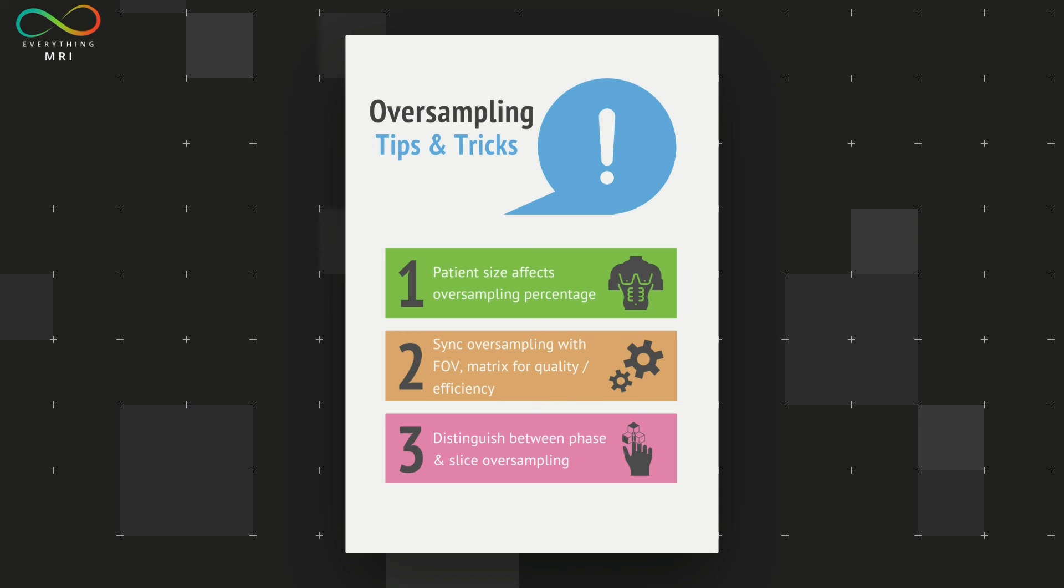Finally, as we mentioned at the beginning, aliasing mainly occurs on the phase encoding. But hear me out, there might also be situations where it can occur between end slices. And this predominantly happens when we acquire 3D sequences. In volumetric imaging, in fact, if the image volume extends beyond the field of view in the slab select direction, the phase wraparound artifact might occur between slices at the ends of the 3D partition.